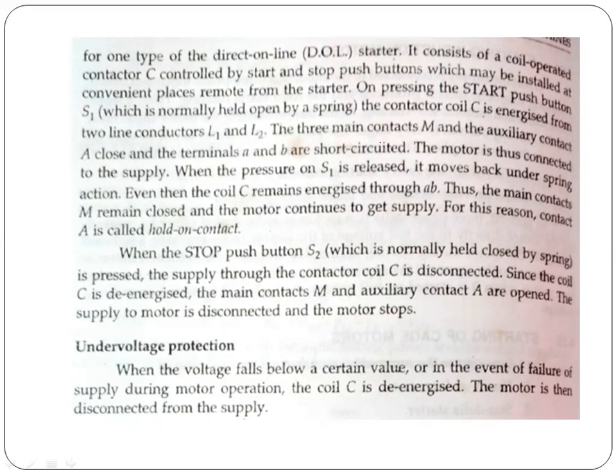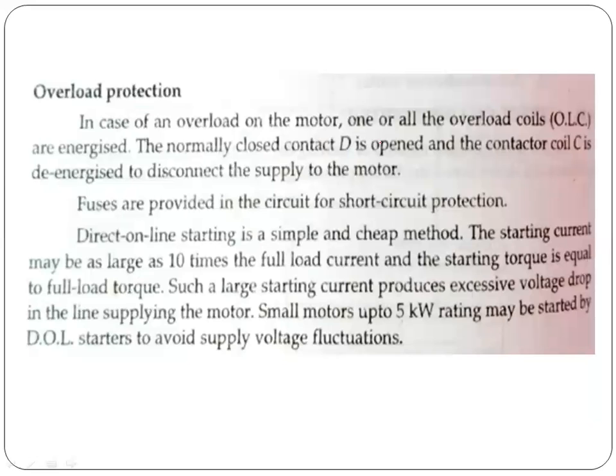When the voltage falls below a certain value or in the event of failure of supply during the motor operation, the coil C is de-energized. The motor is then disconnected from the supply and that's why it gives us the under voltage protection. Overload protection: in case of an overload on the motor, one or all the overload coils are energized. The normally closed contact D is opened and the contactor coil C is de-energized to disconnect the supply to the motor. Fuses are provided in the circuit for short circuit protection.